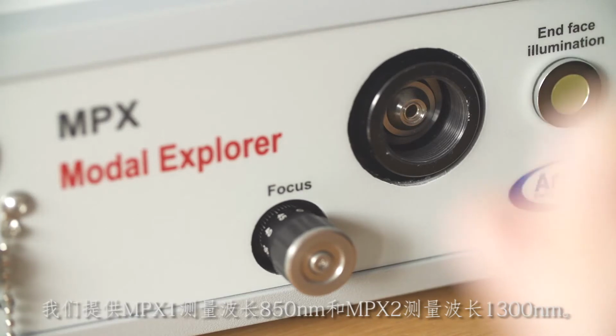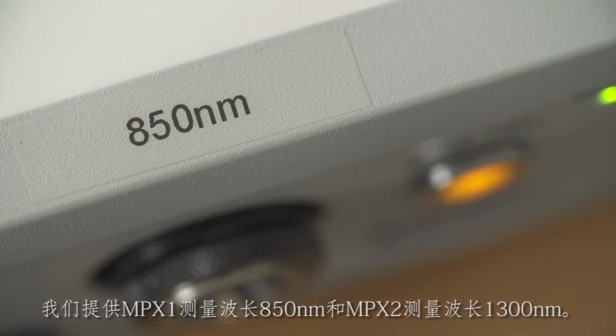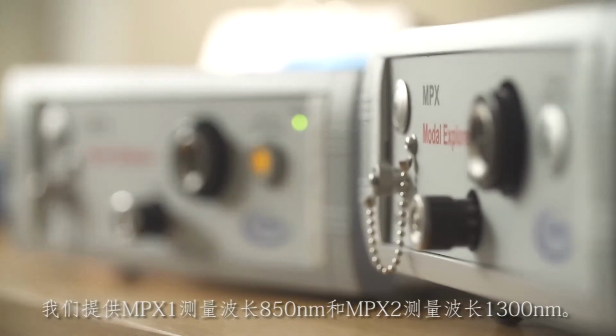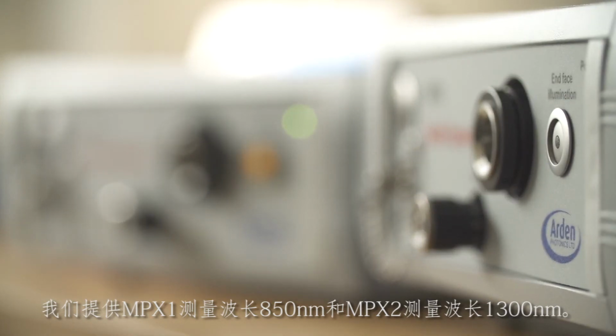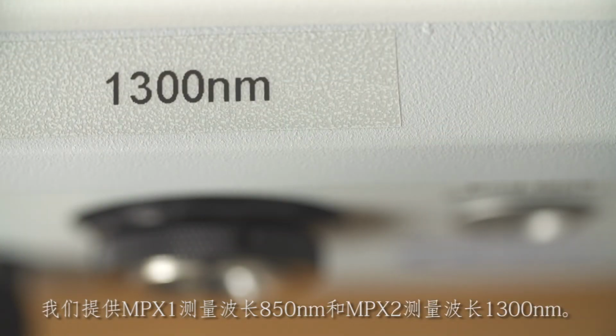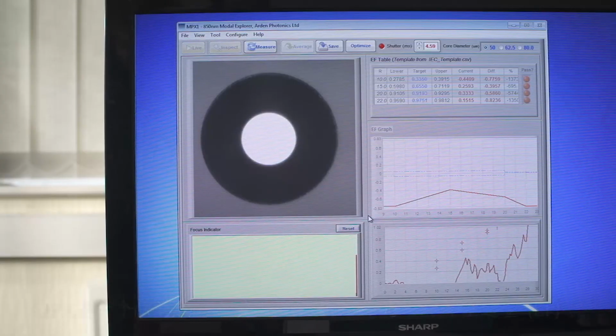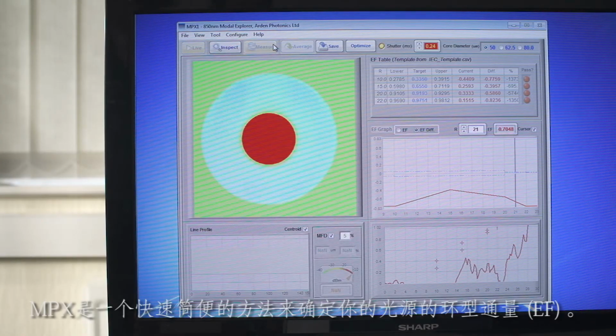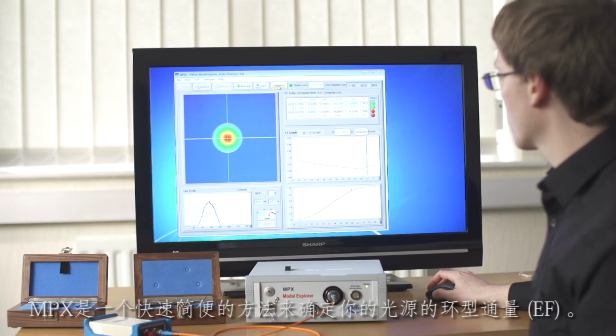We offer the MPX-1 measuring at a wavelength of 850 nanometers and its heavier sister, the MPX-2, for measurements at 1300 nanometers. The MPX is a fast and easy way to determine the encircled flux of your light source.